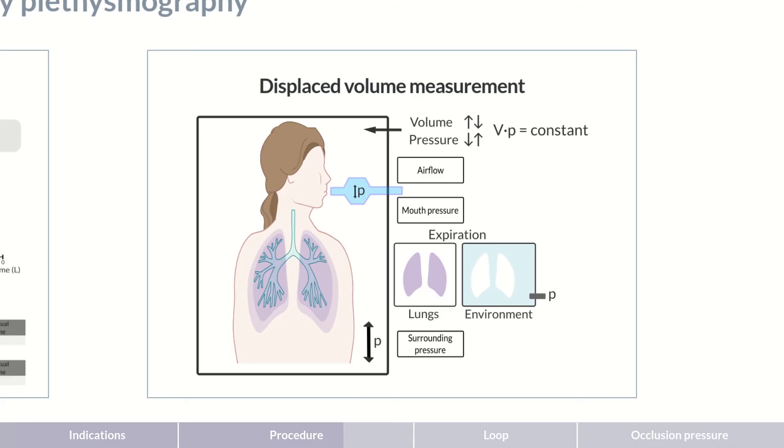Through this interplay, the change in thoracic volume can be derived from the change in cabin pressure. The product of volume and pressure before inspiration must remain constant and therefore equal to the product of volume and pressure after inspiration.